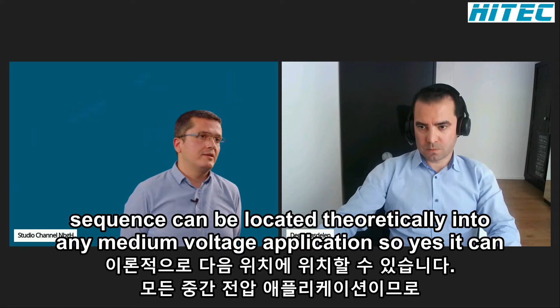And while Deir is checking for more questions, I see one that I find interesting, even if I do not understand the details. The question was, what will protect the upper zone in the busbar compartment in the area before the arc quenching devices? This is your area of expertise. Without having an arc flash protection, what are the old conventional methods for such protection? The thing is, so-called intertripping signals are sent to the upstream circuit breaker.